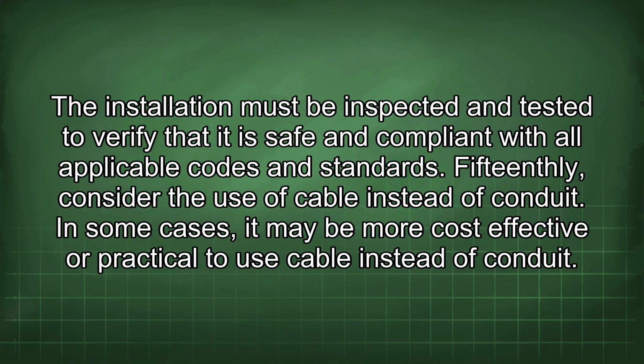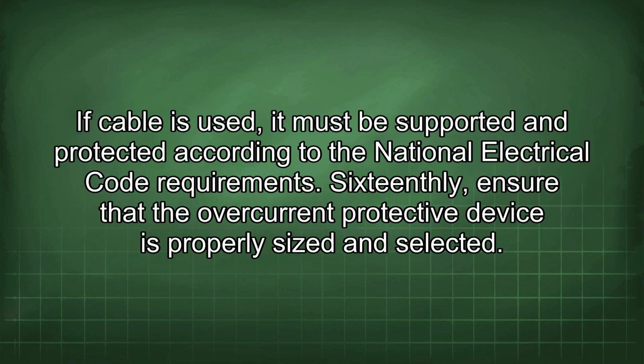15thly, consider the use of cable instead of conduit. In some cases, it may be more cost-effective or practical to use cable instead of conduit. If cable is used, it must be supported and protected according to the National Electrical Code requirements.